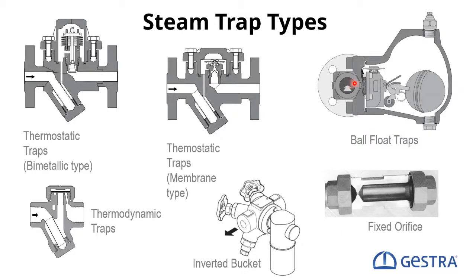And yes, last year I found some which were more than 60 years in operation, and that is a long lifetime. Looking at the bimetallic steam trap, we still have the version from 1970 in some customer refineries, which were working. If the condensate is clean, the filter is not blocked anyhow, and we have no water hammer, then this type of steam trap also has a very long lifetime, and because of its subcooling up to 25-30 degrees Kelvin distance to the saturation curve, the leakage of steam is in the first years more or less zero.